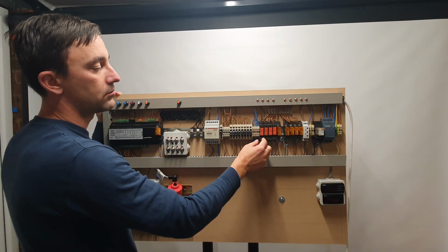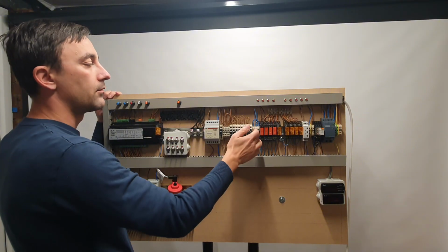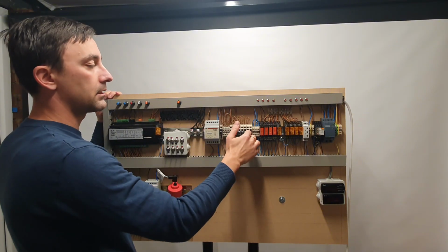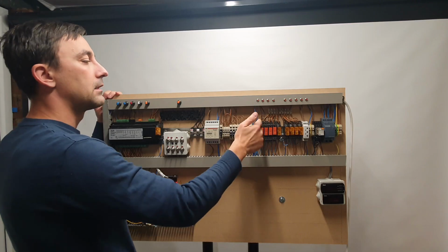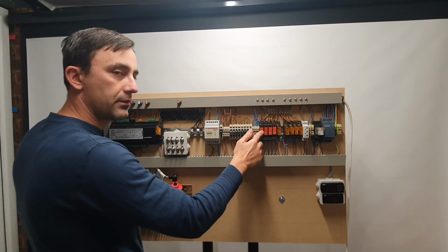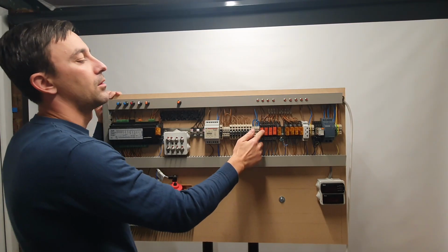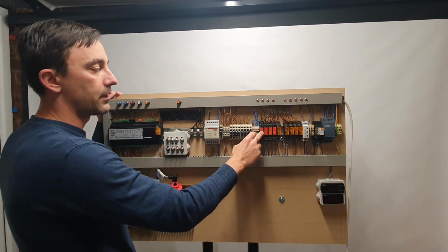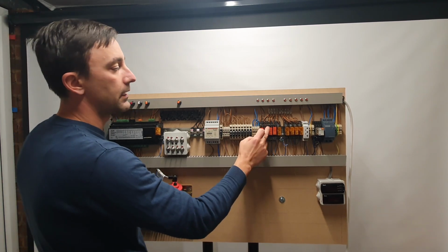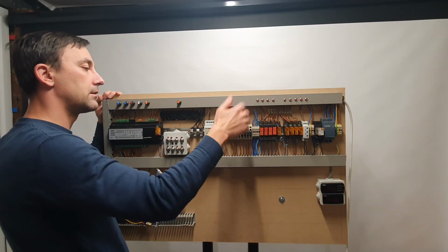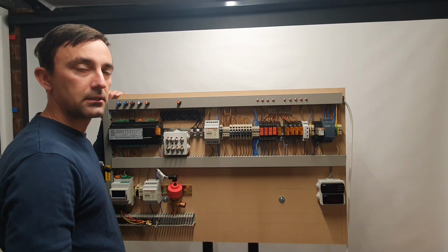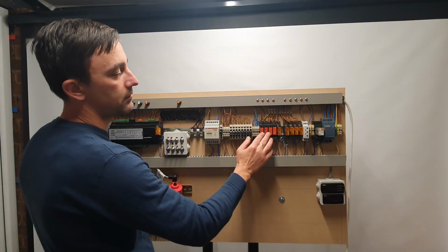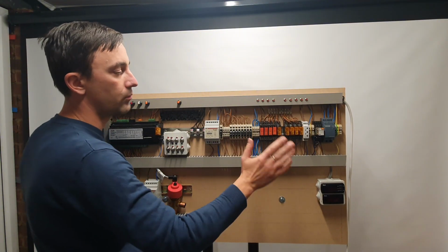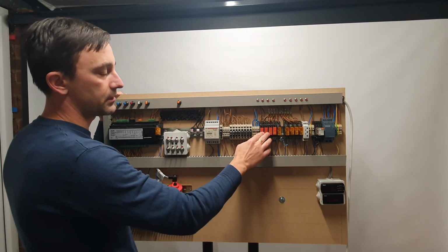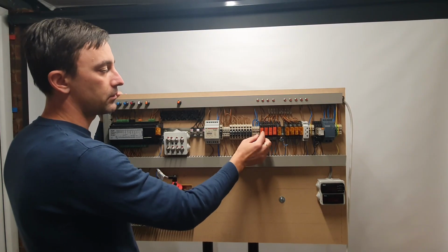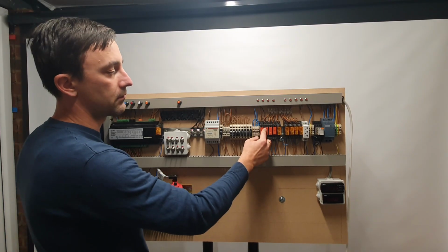I just wanted to show that if the safety circuit is healthy, that in turn will energize the safety relay, which is a condition to operate the compressor relay, that in turn will energize the contactor and then give power to the compressor. So that's the reason for compressor number 1. It's just a different way of wiring. I chose for compressor number 1 to use 2 relays, one for the safety circuit and one for the running of the compressor.